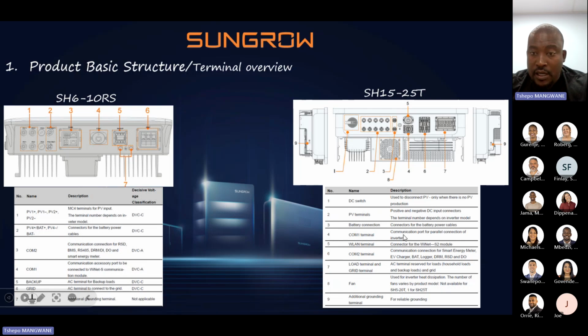For terminal 4, it's our comms port as well. Comms port for CAN high and CAN low, RS485. We mainly use this COM port for paralleling the inverters, mainly daisy chaining. If you have more than 2 or 3 inverters, then we use the COM 4 to parallel and put our 120 ohm resistors on CAN high and CAN low. We terminate also with the RS485 daisy chain to the other inverter. All this information is there in the manual as well. Okay. Port 5, it's where we plug in our WiNet-S Wi-Fi dongle.